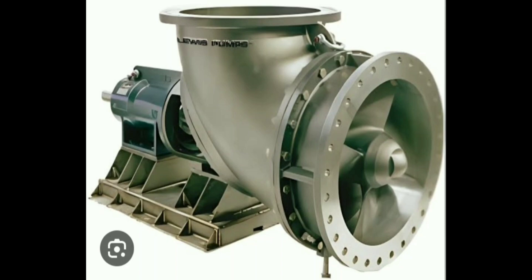Let us look at the disadvantages of an Axial Flow Pump. It is not suitable for applications requiring high pressure generation. Performance can be affected by changes in system conditions. It has a specific application range — best suited for high flow and low head requirements, meaning high flow rate and low pressure.